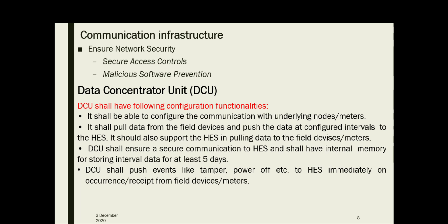The DCU shall ensure secure communication to the head-end system and shall have internal memory for storing interval data for at least five days. It shall pull data from field devices and push data at configured intervals to the head-end system. DCU shall also push events like tamper or power off to the head-end system immediately upon occurrence, received from field devices or meters.